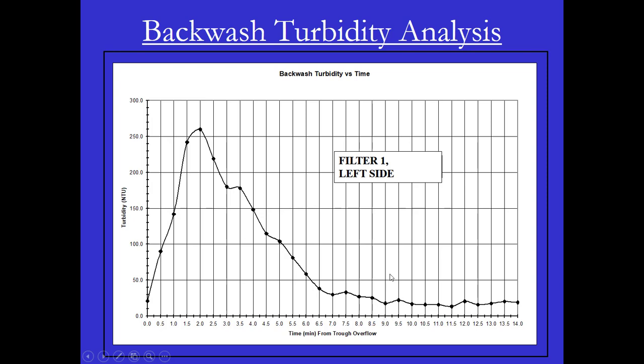Chances are you should be able to reduce that backwash time by maybe four or five minutes. What I would do is initially stop the backwash at maybe 12 minutes, then watch the filter over the next week or two to see how it performs. Then maybe cut another minute or two off and wait again. Try to get it back to about nine minutes and save all that wash water.